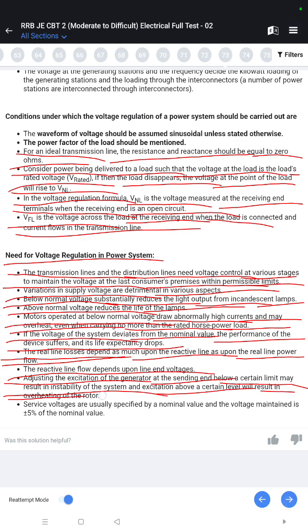Adjusting the excitation of the generator at the sending end below a certain limit may result in instability of the system, and excitation above a certain level will result in overheating of the rotor. Service voltage are usually specified by a nominal value, and the voltage maintained is plus minus 5% of nominal value. Ferranti effect on long overhead line is experienced when it is no load condition.